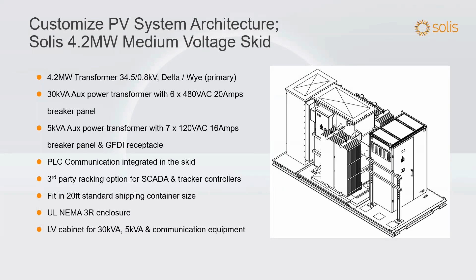What you want to put that piece in front of is the big skid that Solis now has. You can set these skids up, they come in a 20-foot container, and you just drop them right on a pad in a central location for a repowering array or a new array. If the installers for a particular EPC are used to setting up centrals, we can use the modularity, reliability, and extra MPPTs you get with PV string inverters to create essentially a central inverter architecture.